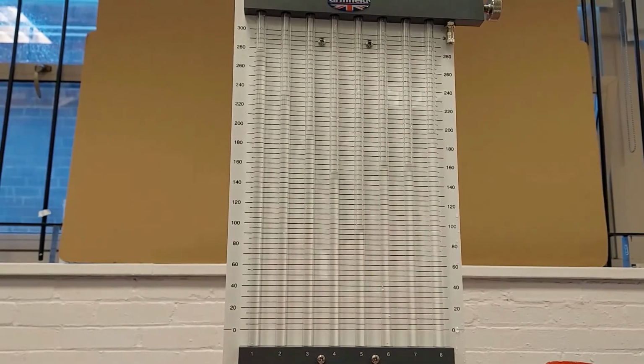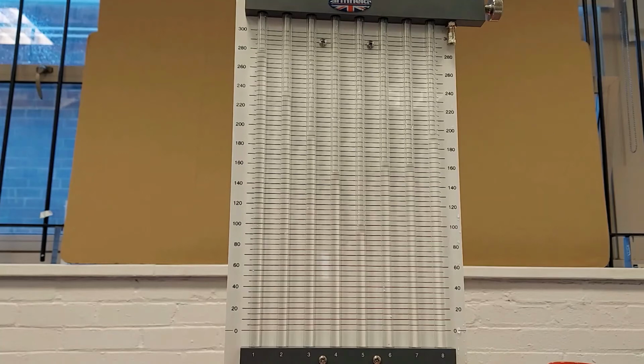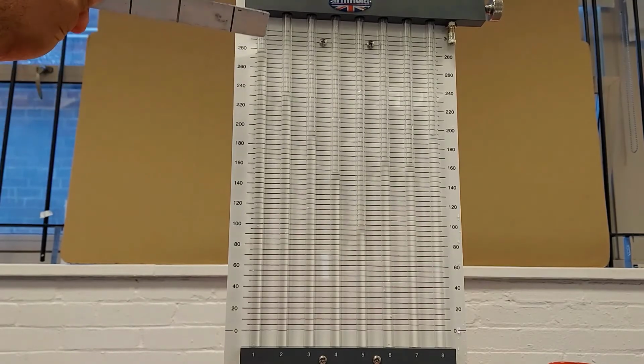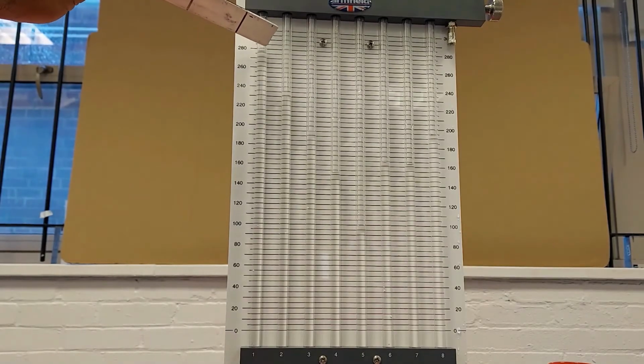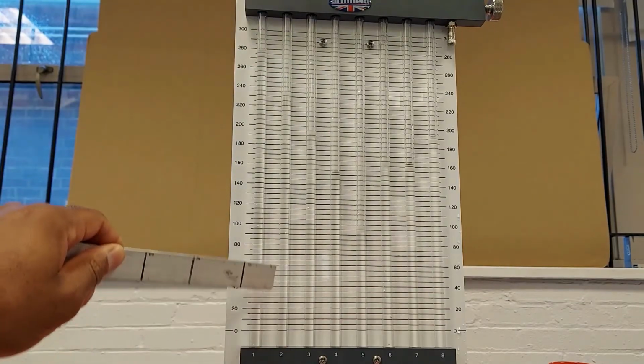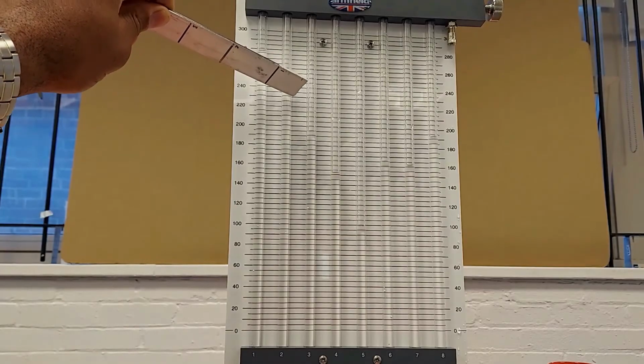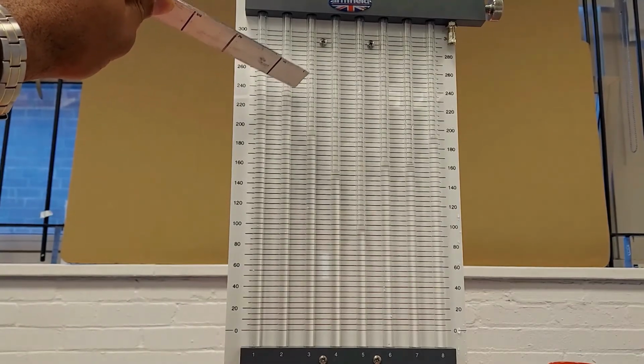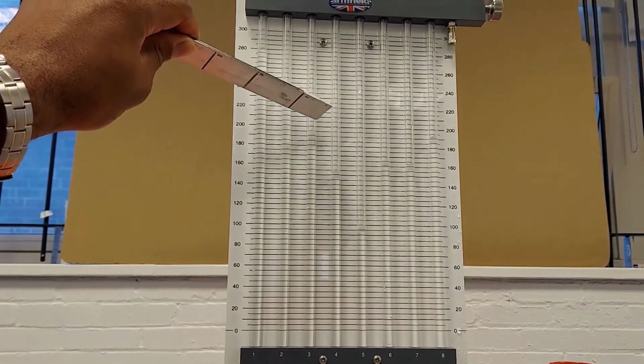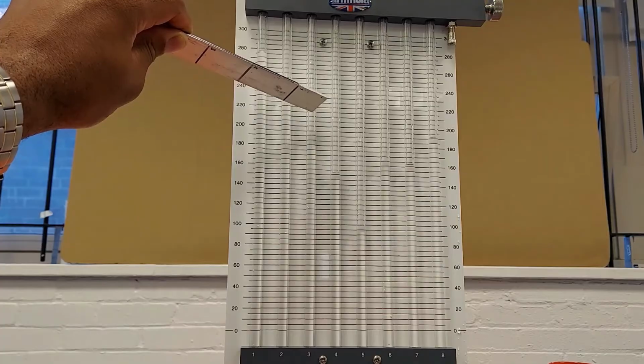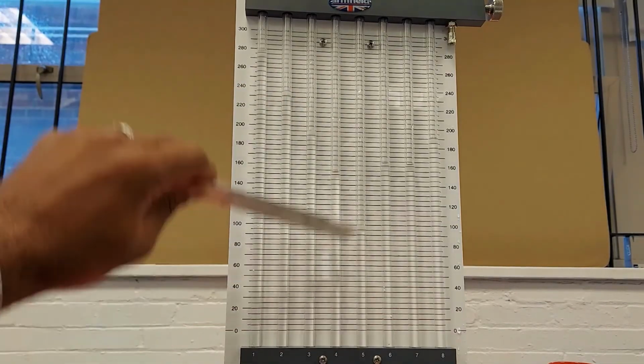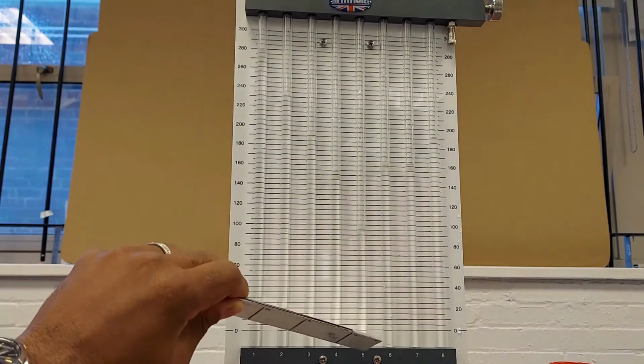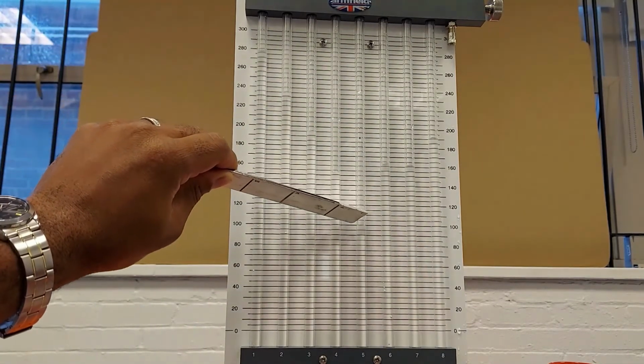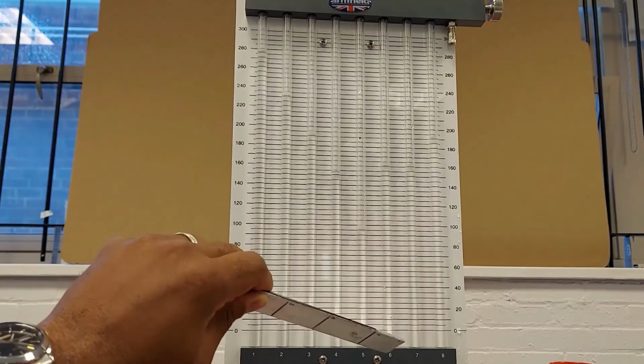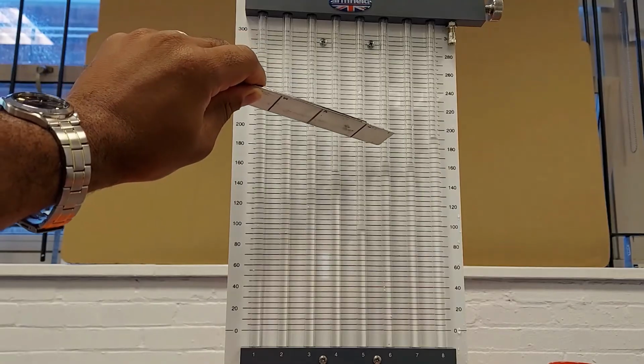Now that we have acquired our flow rate, what we would do next is to take readings of H1 to H6. So H1, we are at roughly 275. H2, we are at 230, 235. H3, we are at 194. H4, we are at 152. And H5, we are at 99. And H6, we are at 164.